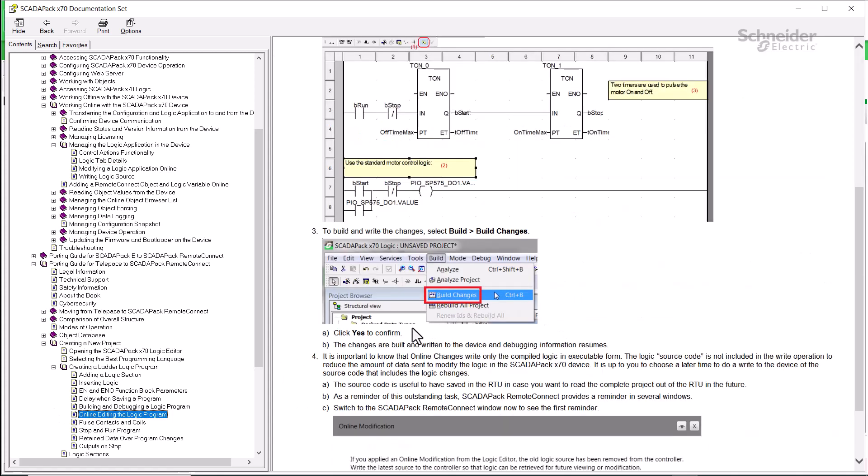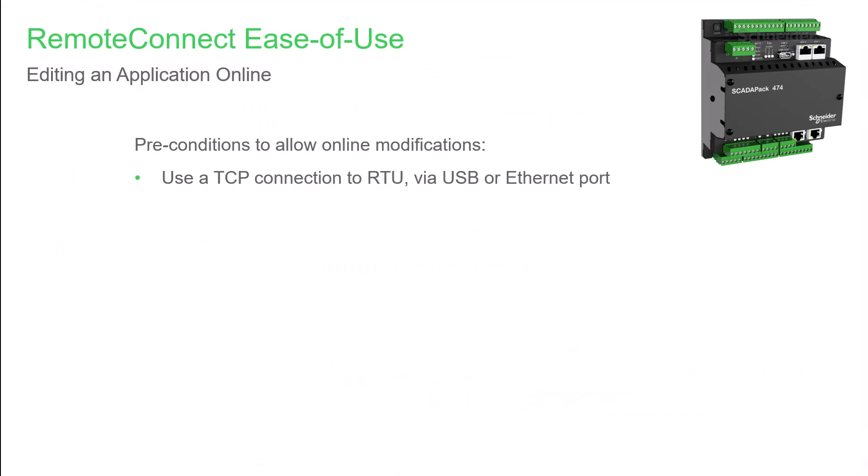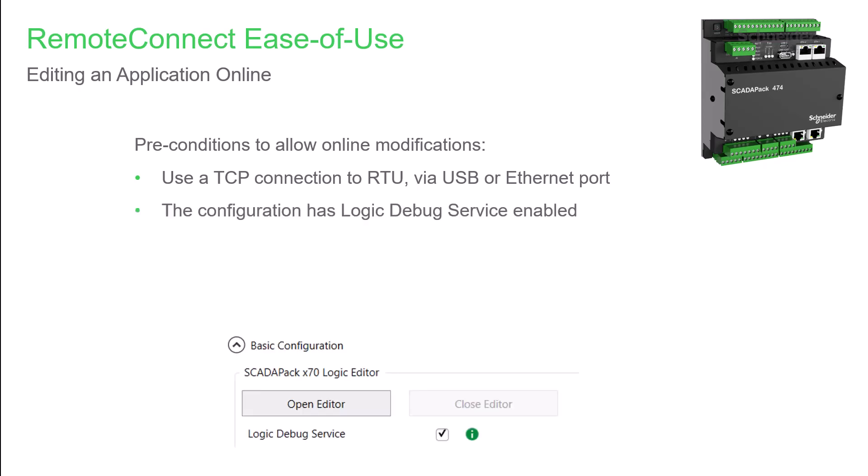This walks you through the basic steps of modifying logic online. Before starting to do any online editing, here are some conditions to meet. First, the communication channel needs to use TCP, either USB or Ethernet. The logic debug service box needs to be checked. This is the default.